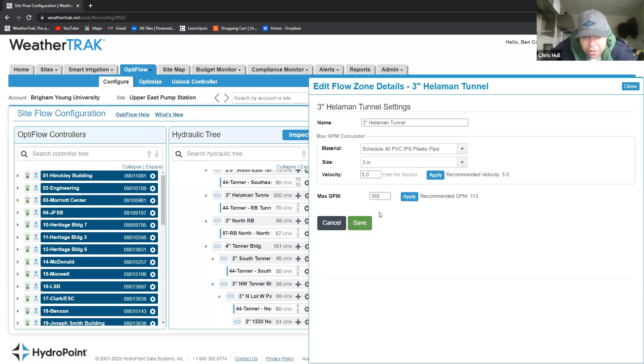And when you go into optimize, you can make that flow last 350 gallons a minute, and you can make it go from 7 until 7 in the morning. Instead of having a huge peak at night where, if you had like 700 in there, you'd have a huge peak at like 10 o'clock until 2, you could shorten your water window that way. But if you have a water window that's extended, then you can incorporate that flow in there so you can establish how long you want that water to run.